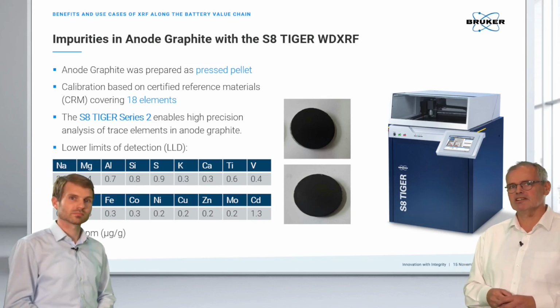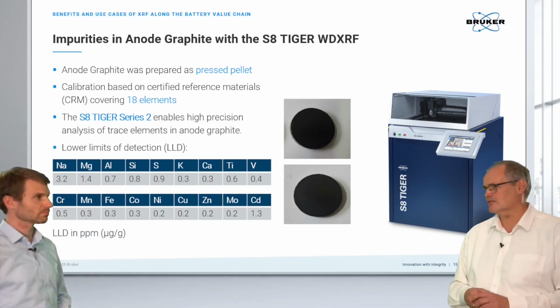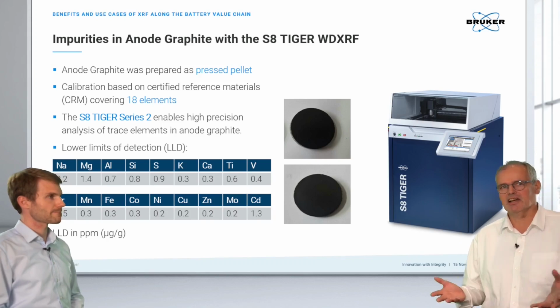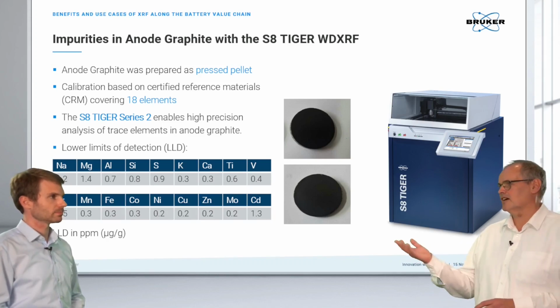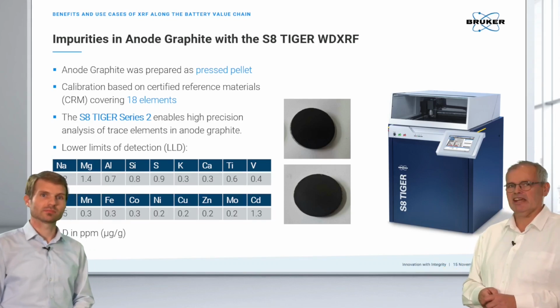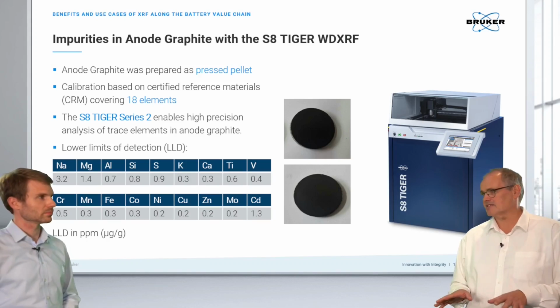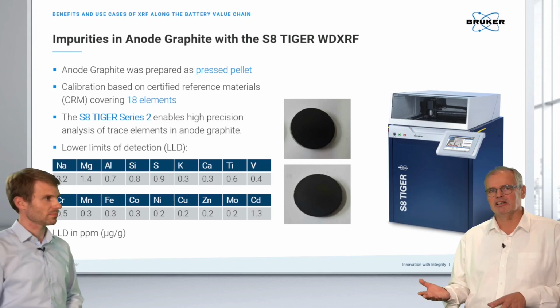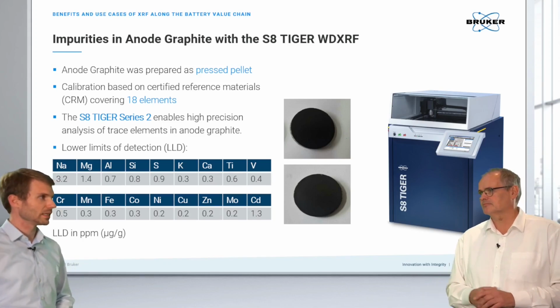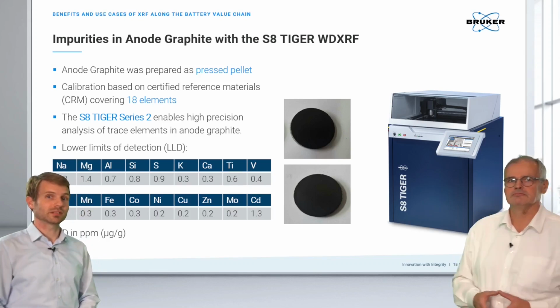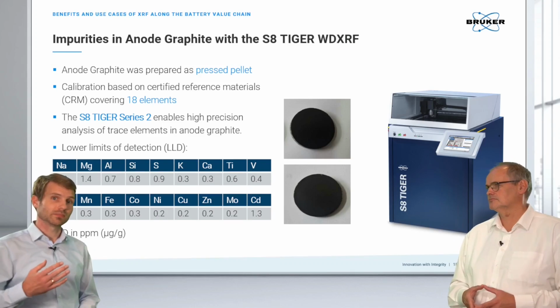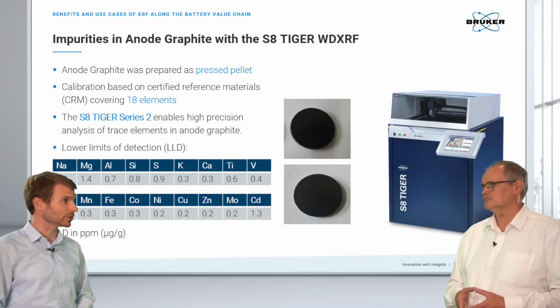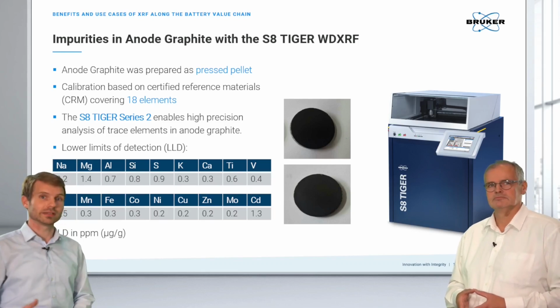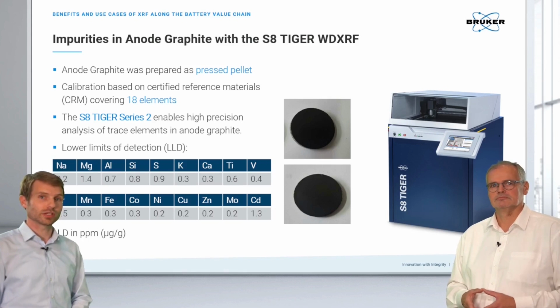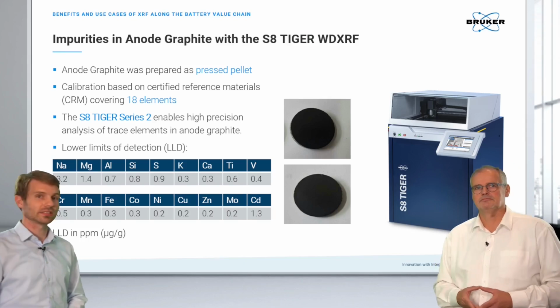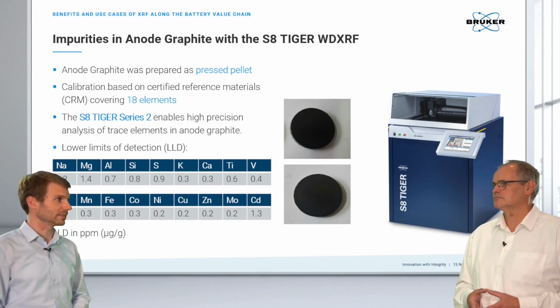You see here, it's very easy. We press the graphite powder with a little bit of wax into a pressed pellet, and then analyze and see directly cobalt starting from 0.3 ppm, which is excellent. So the purity can be easily assessed, and you can control whether the incoming material is according to spec or not, right? Some of these elements can really be quite dangerous when it comes to battery lifetime and battery safety, like sodium, which can cause overheating of the battery. So there you really want to get to really low concentrations to ensure that your battery performance is also right. And this also gives you the strength to really evaluate suppliers that provide your graphite.